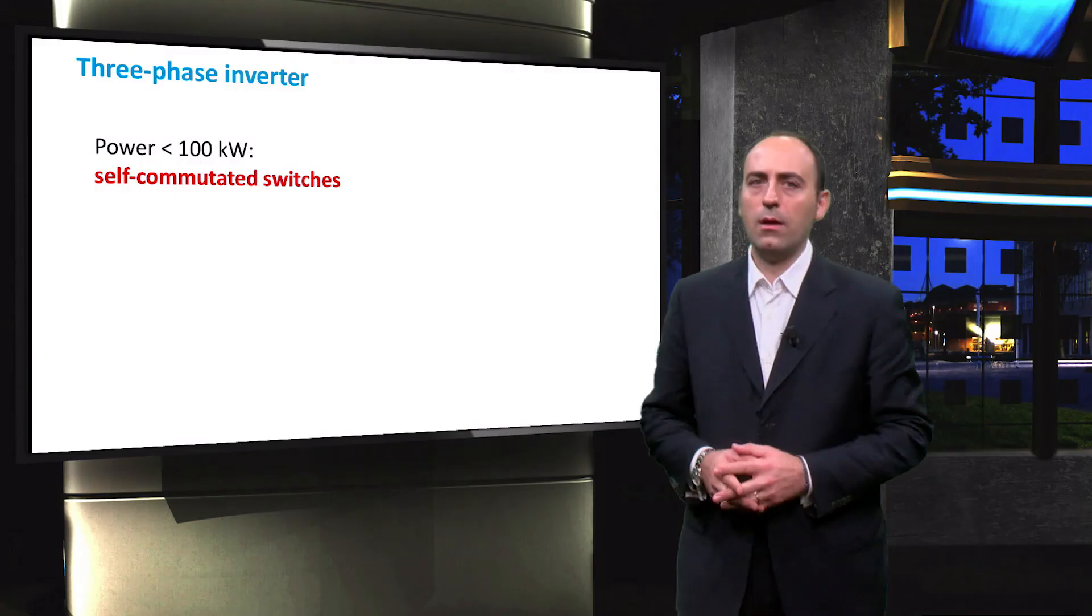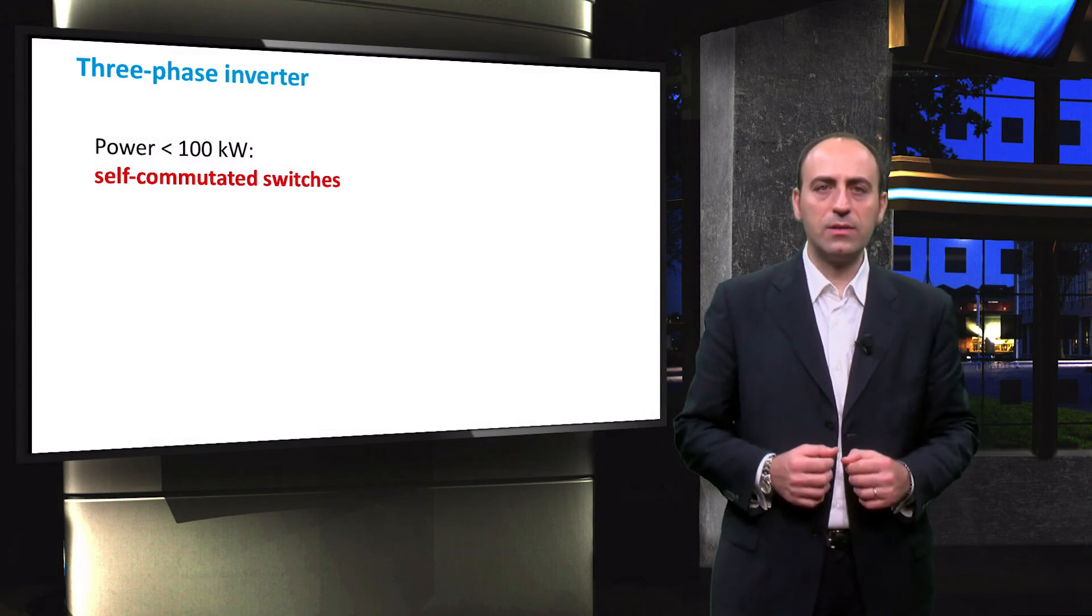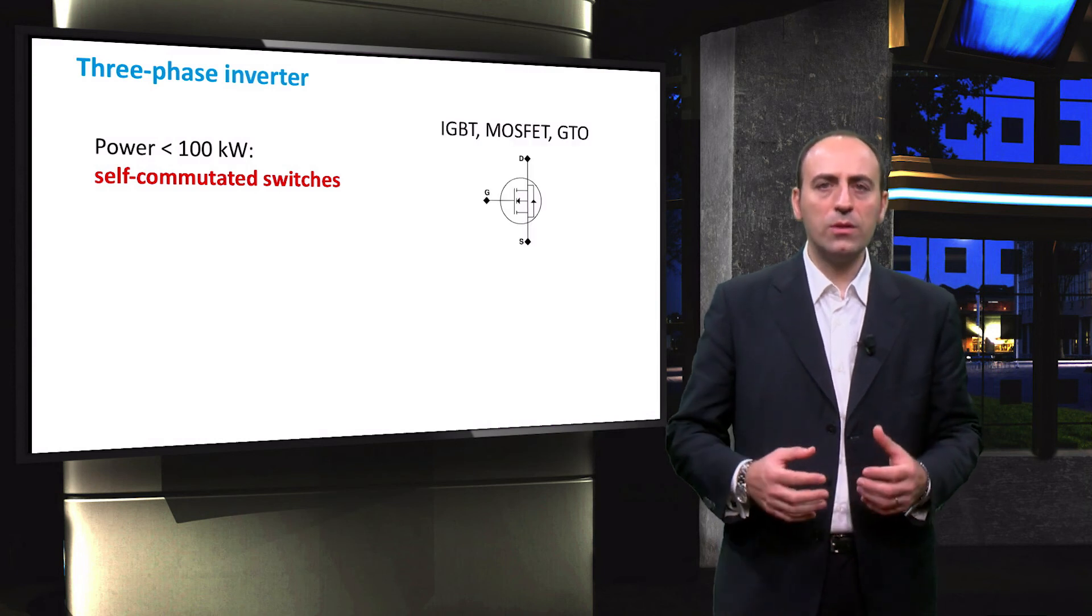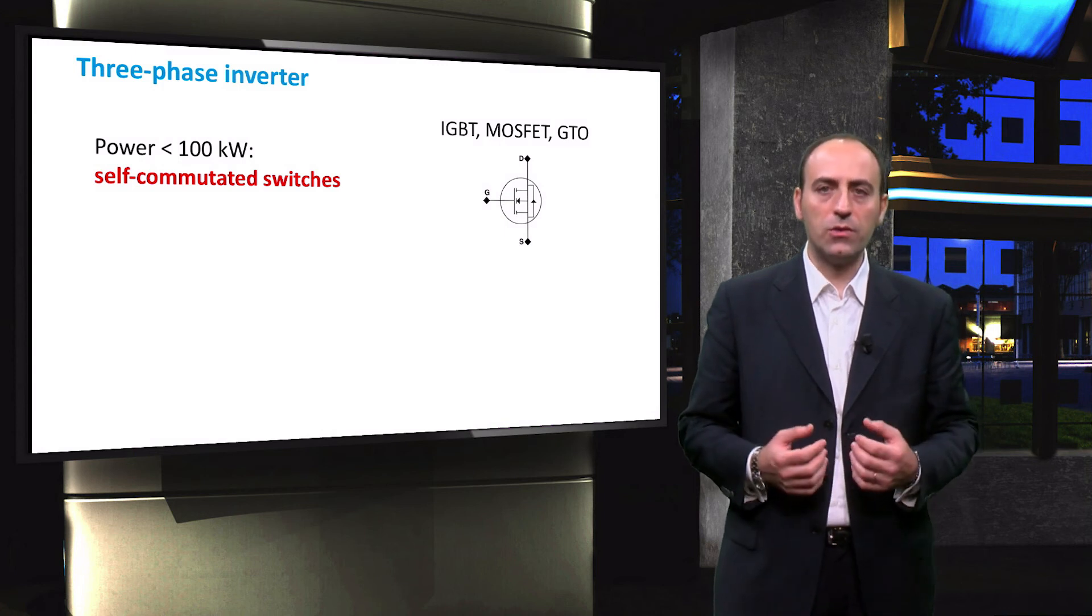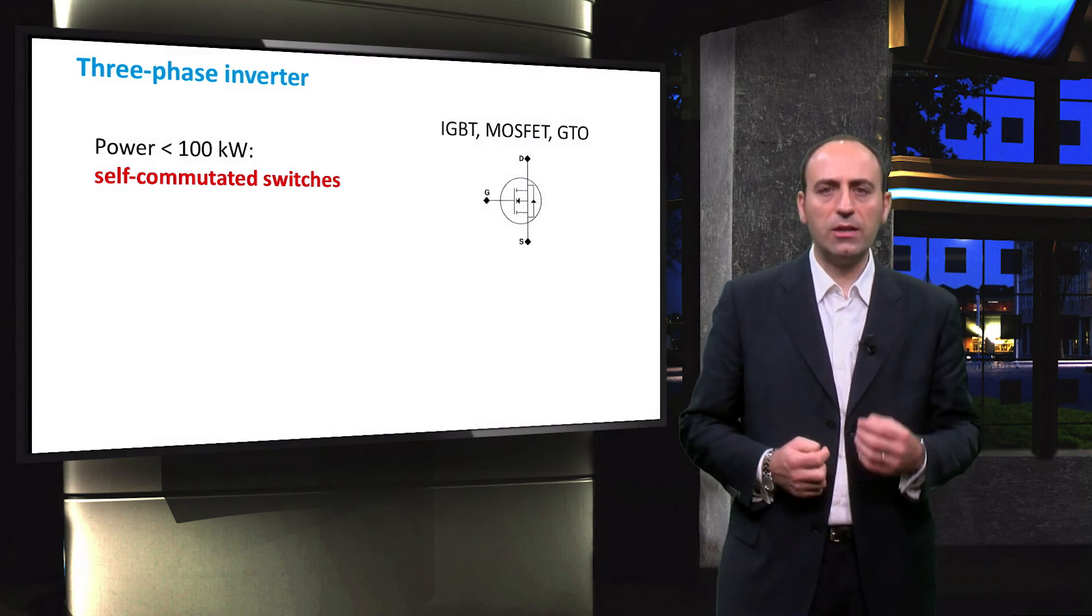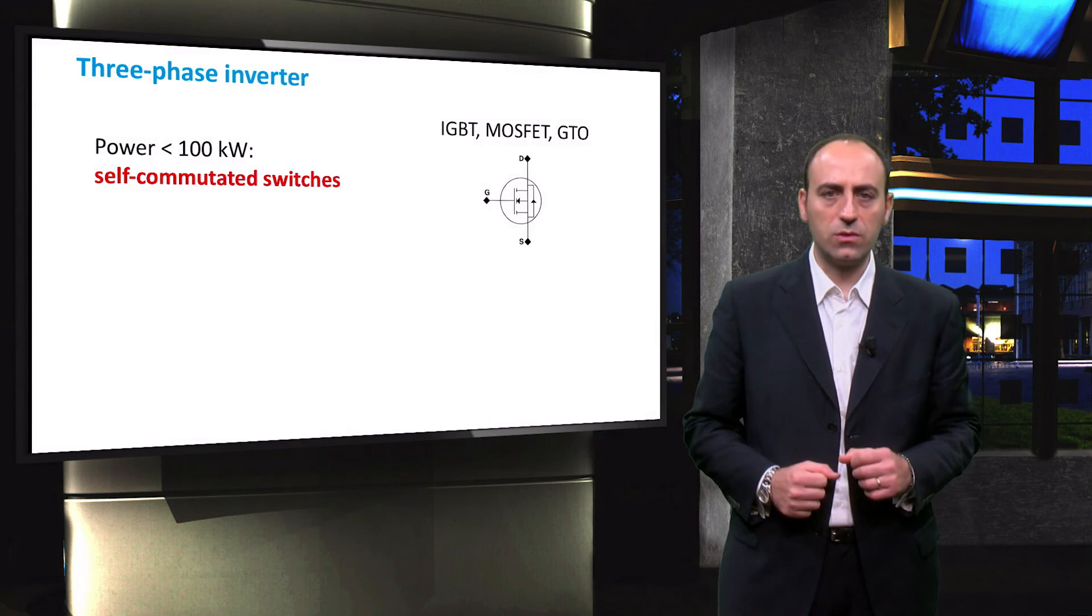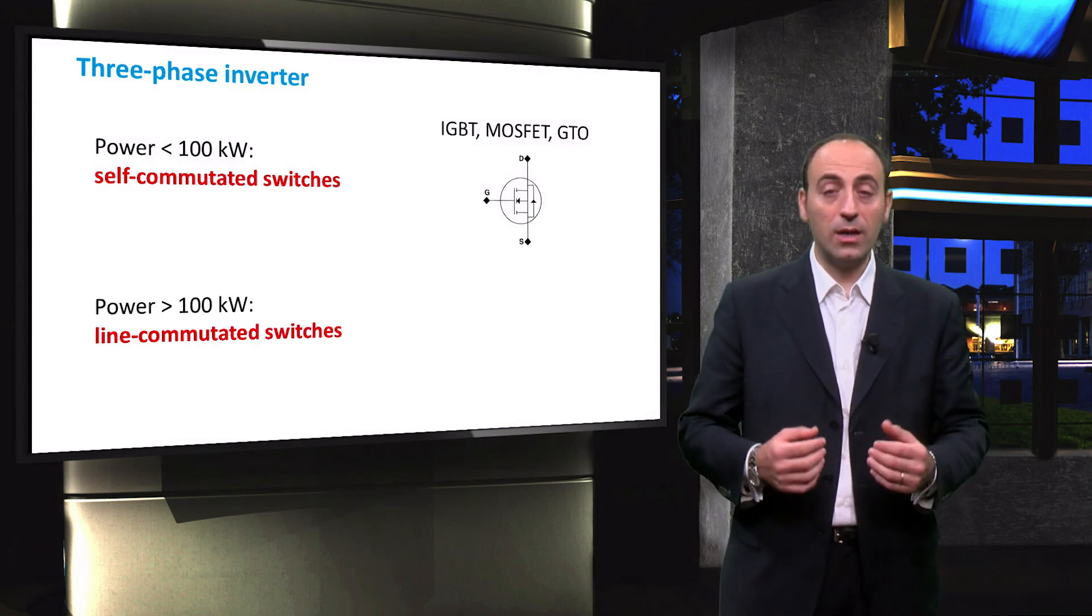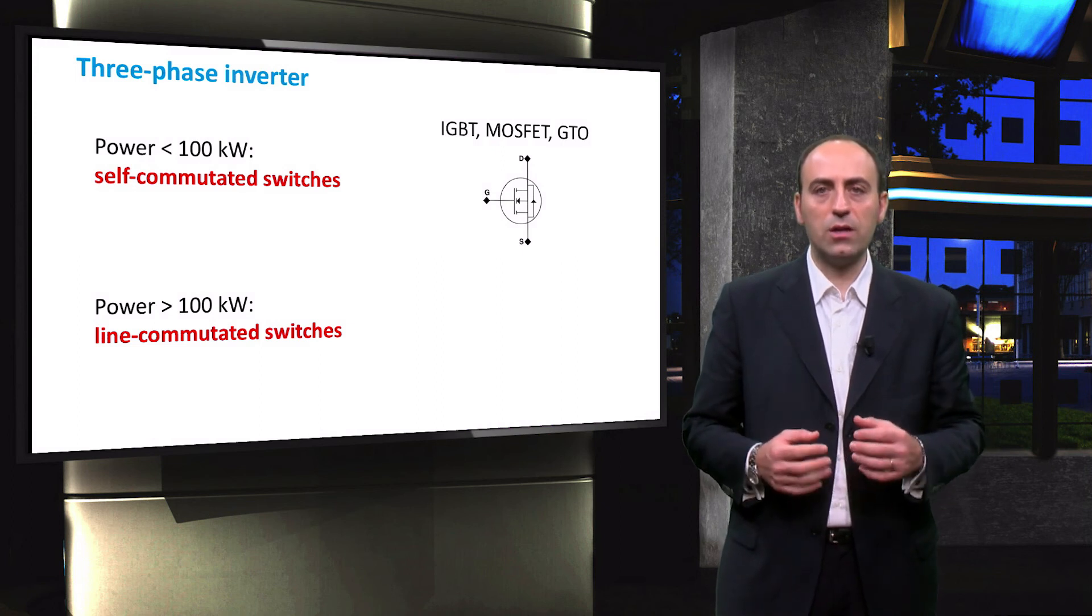If the power converted from DC to AC is less than 100 kW, the switching devices used are usually self-commutated ones. Among these devices, we can mention the IGBT, the MOSFET and the GTO, among others. These devices are characterized by very fast switching and feature a controller that takes care of the opening and closing of the transistors.